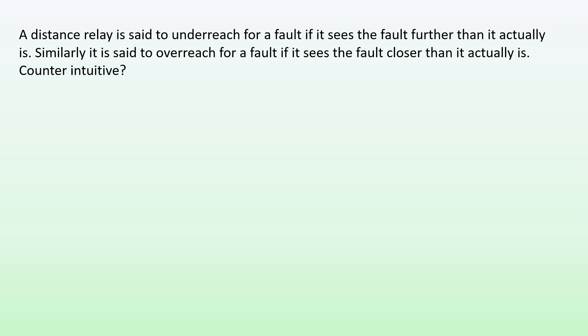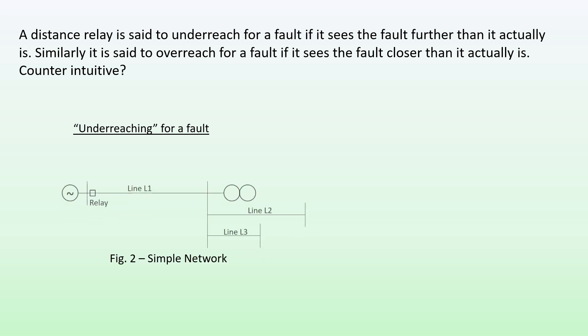A distance relay is said to under-reach for a fault if it sees the fault further than it actually is. Similarly, it is said to overreach for a fault if it sees the fault closer than it actually is. This may seem counterintuitive, but it will become clearer as we move along.